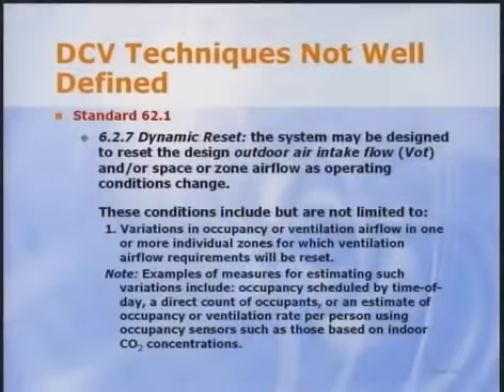From a practical standpoint, I would argue that occupancy schedules and occupancy sensors could be used only to enable the full design outdoor air rate when people are scheduled or sensed to be present, and allow ventilation to be shut off when people are not present. These two measures could not allow a partial reduction in ventilation rate because only the presence of people is known, not the number of people. To partially reduce outdoor air rates during occupied periods, either a people counting device must be used, although certainly that's not a common approach, or CO2 concentration must be used. I'm going to focus on CO2-based demand control ventilation since it is the most common approach.